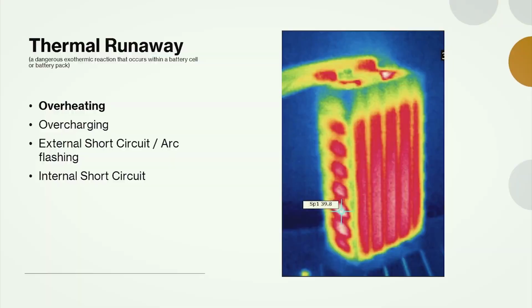So those are things that could cause thermal runaway from an external source. When we look at the battery itself, users might think, my battery system is doing fine, I've protected it from vehicles crashing into it or similar things, but overheating could still happen internally when visually you might think the system is fine. Overcharging is the same — those are failures we don't see visually.